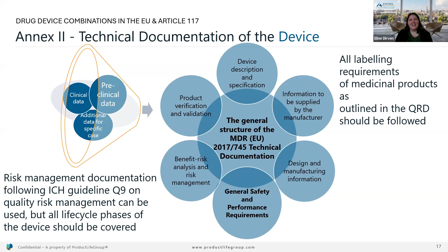But this is, for instance, that you don't need to forget about your sterilization validation data, or the accuracy data for the measuring function. That all needs to be included as well. So once you've done your exercise, so you've filled in your GSPR checklist, you have also all your evidence ready, then you can compile your technical documentation. You can also prepare a cover letter, which will ease the completeness verification for the notified body. And if certain parts or subparts are not applicable, then please just provide a short explanation.